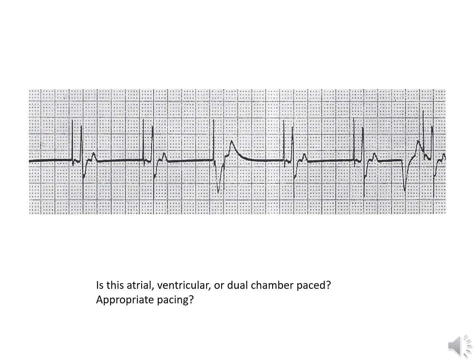Now let's look at the ventricular. The ventricular is the spike deflected downward. Where we really see an issue with it is in the third complex. When you look at the third complex, you have a pacer spike after the QRS. So that is a problem with sensing. The pacemaker does not see the patient's own intrinsic beat. So you want to adjust the sensitivity. Because the patient's own intrinsic beat is there and the pacemaker does not see it, we want to lower the fence and bring the fence down so we can see more of what is going on with the patient's own beat. So this is a problem with failure to sense.